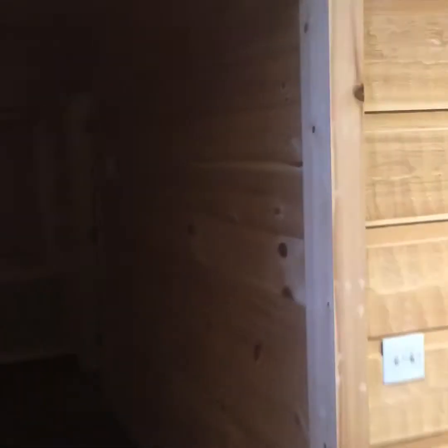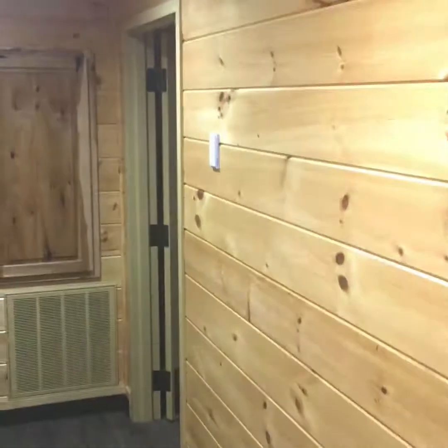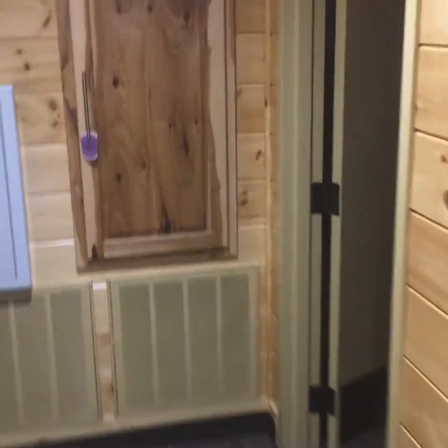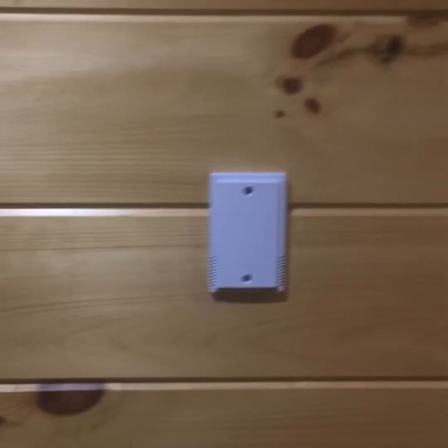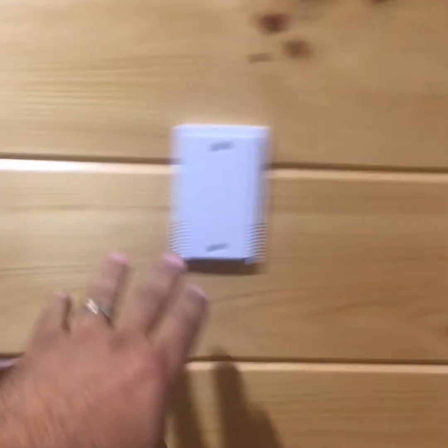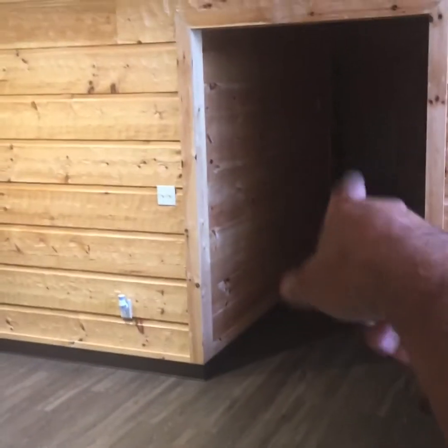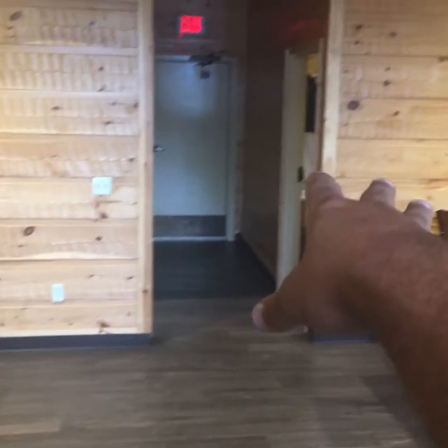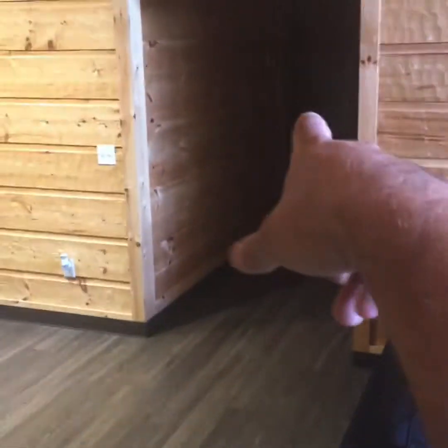One other quick thing on these units. When we designed the HVAC or thought it out, these were originally bunk rooms with kids. So here is your remote sensor for the unit that basically conditions these two bunk rooms, and then also half of this main room here. What has happened on a couple of these is one of these units can kind of run off and leave the other one.